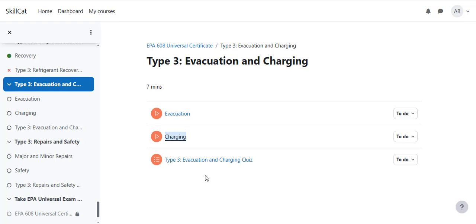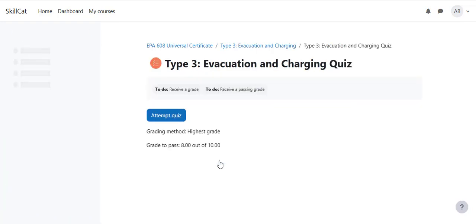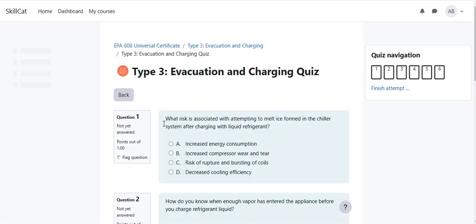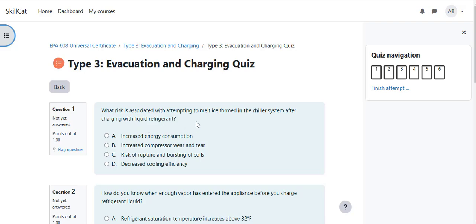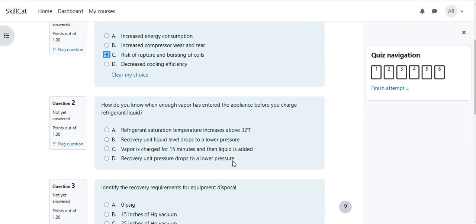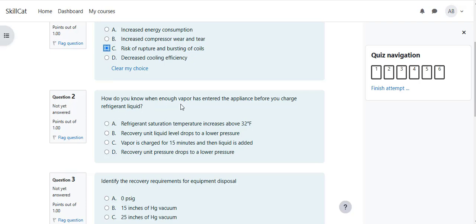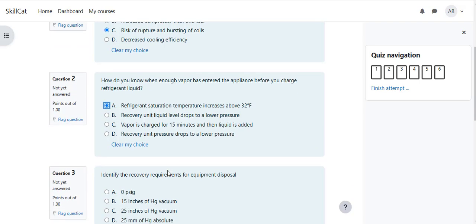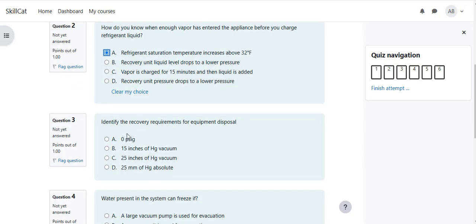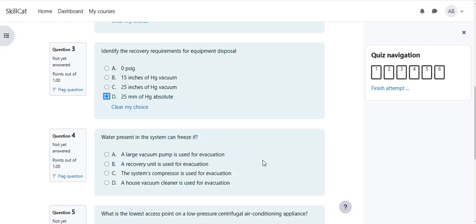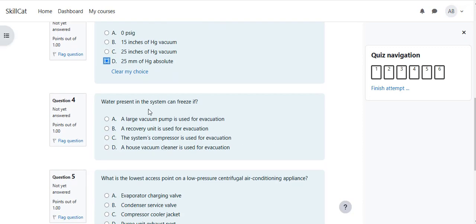Okay, let's go to evacuation and charging quiz. Okay, what risk is associated with attempting to melt ice formed in chiller system after charging with liquid refrigerant? The risk of rupture and bursting coil. How do you know when enough vapor has entered the appliances before you charge refrigerant liquid? Refrigerant saturation temperature increase above 32. Identify the recovery requirement for equipment disposal. It's 25 millimeters of Hg absolute. Water present in the system can freeze if.